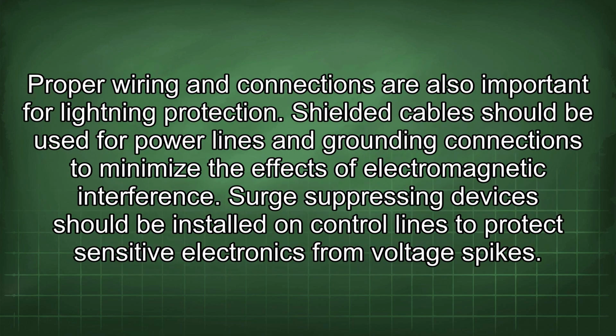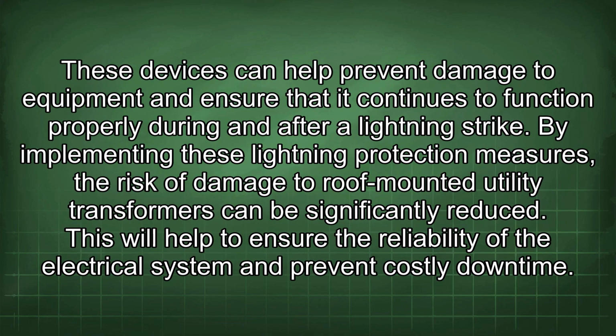Proper wiring and connections are also important for lightning protection. Shielded cables should be used for power lines and grounding connections to minimize the effects of electromagnetic interference. Surge-suppressing devices should be installed on control lines to protect sensitive electronics from voltage spikes. These devices can help prevent damage to equipment and ensure that it continues to function properly during and after a lightning strike. By implementing these lightning protection measures, the risk of damage to roof-mounted utility transformers can be significantly reduced. This will help to ensure the reliability of the electrical system and prevent costly downtime.